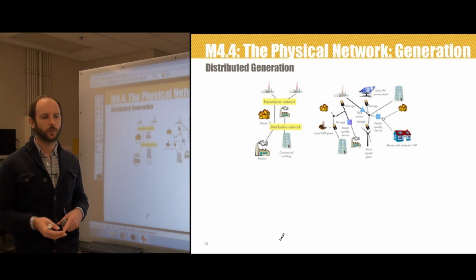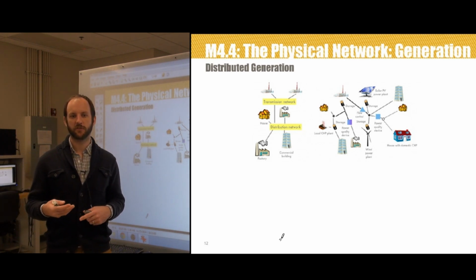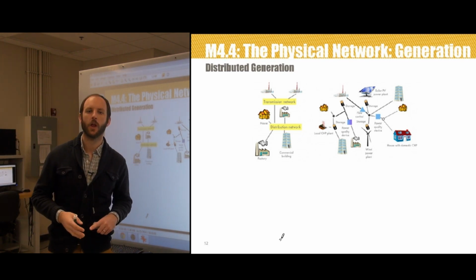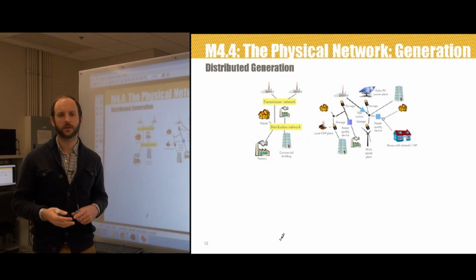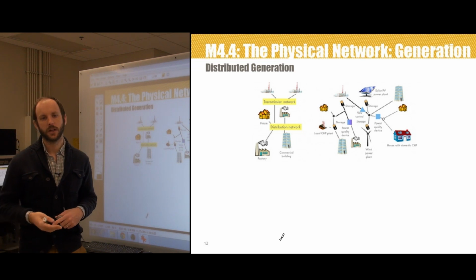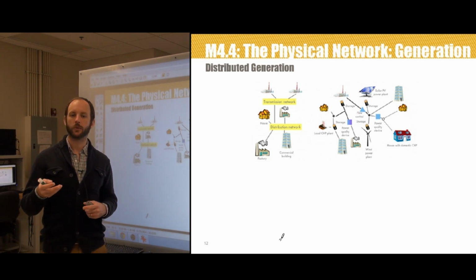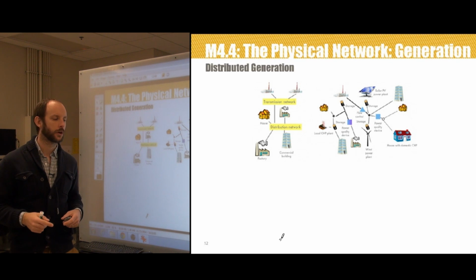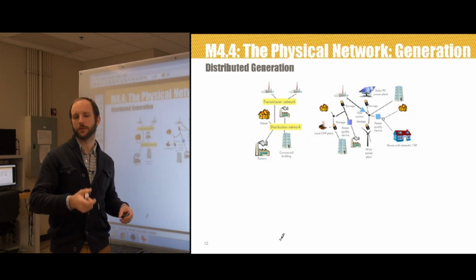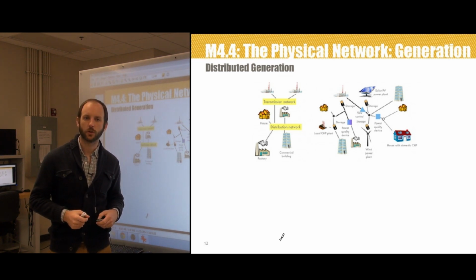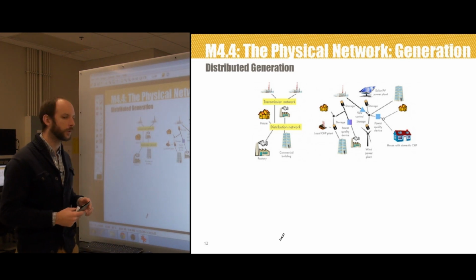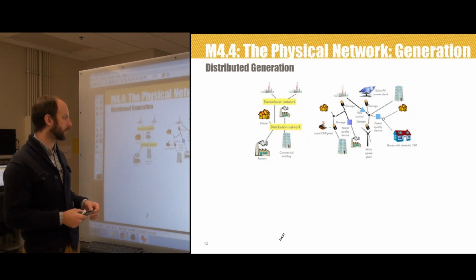The sixth reason we turn to distributed generation technologies is efficiency. The U.S. Energy Information Administration, who we've been taking a lot of this information from, reports that about 7% of the electricity generated is lost in transmission and distribution in the high voltage system. Decrease the distance that it travels and you decrease the amount that is lost. Remember, we know that the resistance of a copper conductor is based on its length. So if we simply decrease the length, we have less total resistance. So those are some of the reasons that we look into distributed generation technologies.